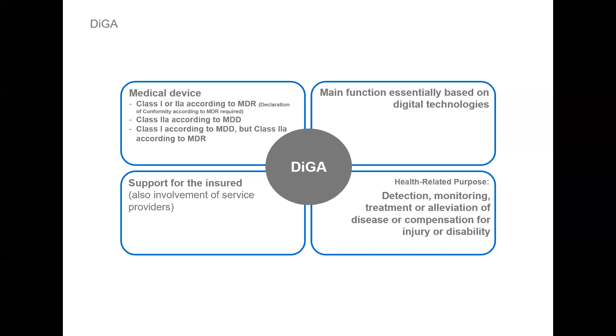Yeah, so as I've already mentioned, if you go through the conformity process as a medical device, if you are class 1, you don't need a notified body. If you are class 2A or higher, you will need a notified body. And this is in a lot of cases a critical point, that as software, according to the medical device regulation, most of the software, to cut it short, will be class 2A or higher. So there's only a few software, like pure training software, that doesn't have a diagnosis or give a treatment itself, that can be classified as class 1 device.